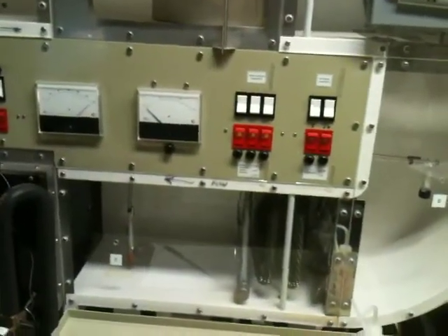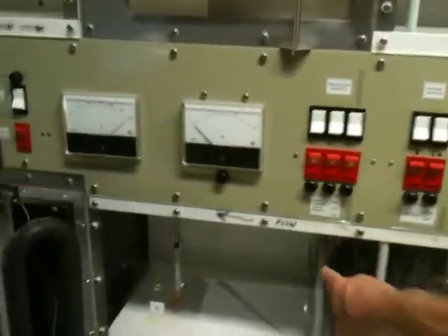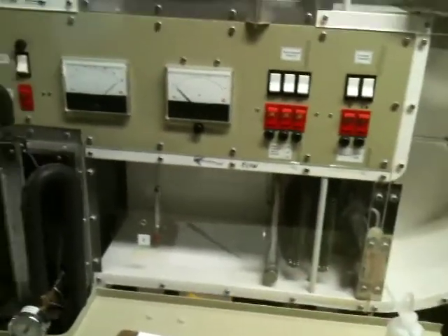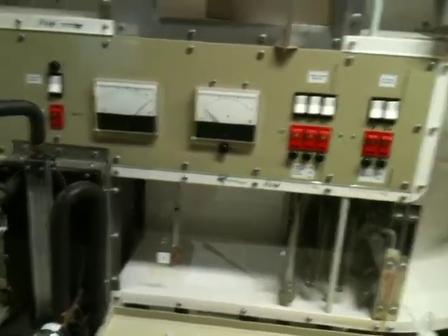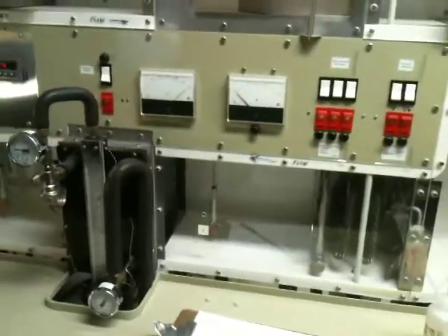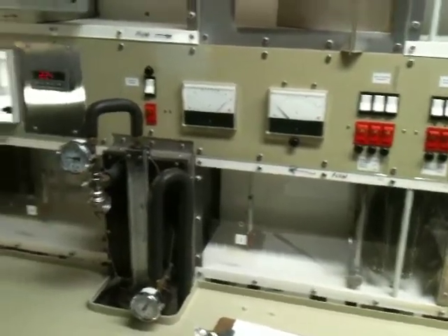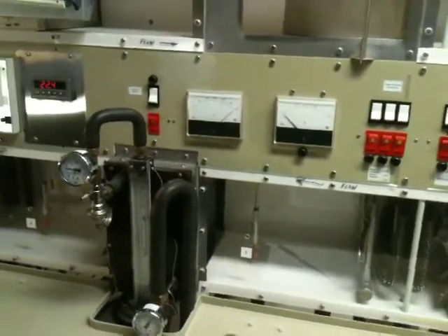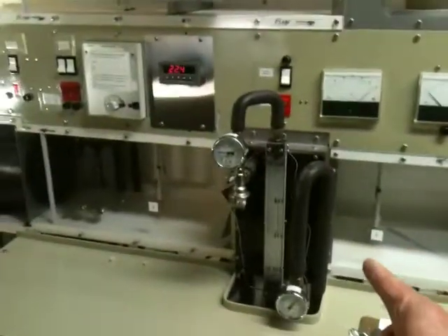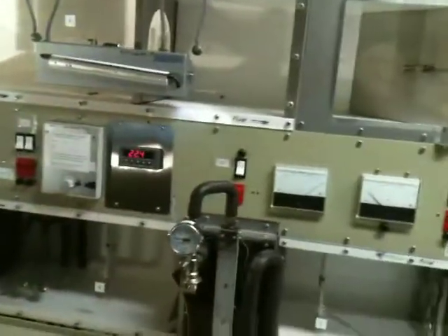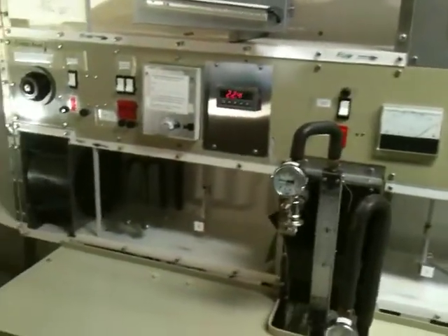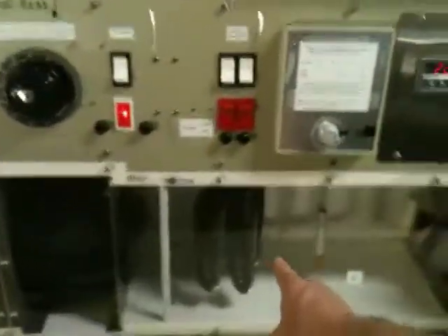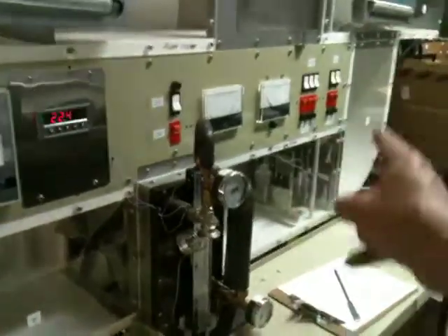For test number 3, we're going to turn off the preheater, but we'll turn on the boilers. So we're going to be injecting moisture into the airflow, and that's it. We'll see what effect that has on those downstream temperature reading stations. For the next test, we'll turn on the cooler, and we will also leave the steam injection running. So we are injecting steam, then cooling the flow. We will take the temperature readings. And then test number 5, we will turn on the reheater while we're keeping the cooler on and the steam injection, and look at that effect.